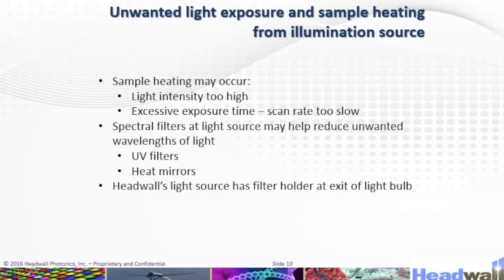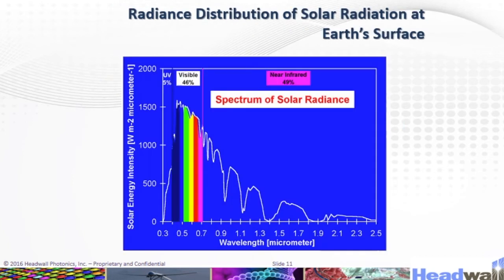Unwanted light exposure and sample heating can occur from the illumination source. Sample heating may occur if light intensity is too high, exposure time is excessive, or scan rate is too slow. A spectral filter at the light source may help reduce unwanted wavelengths of light. Headwall light sources have a filter holder at the exit of the light bulb. Approximately half of solar radiation is in the near-infrared, the other half is mostly in the visible, and about 5% is in the UV. The energy in the mid-wave and long-wave infrared is a very small percentage of total solar energy.